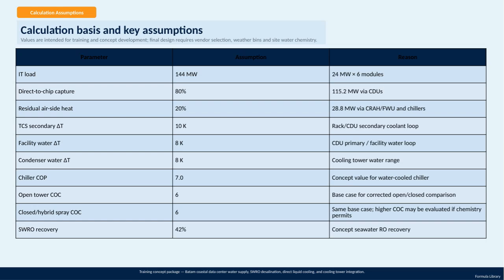Here are the key calculation assumptions for our training and concept development. Keep in mind, these values are preliminary and will need refinement once we select vendors, analyze local weather data, and assess site-specific water chemistry. First, the total IT load is set at 144 megawatts, split across 6 modules of 24 megawatts each. Of this, about 80%, or roughly 115 megawatts, is directly captured at the chip level through cooling distribution units, maximizing direct liquid cooling efficiency. The remaining 20% represents residual heat handled by traditional airside equipment, like computer room air handlers and chillers.